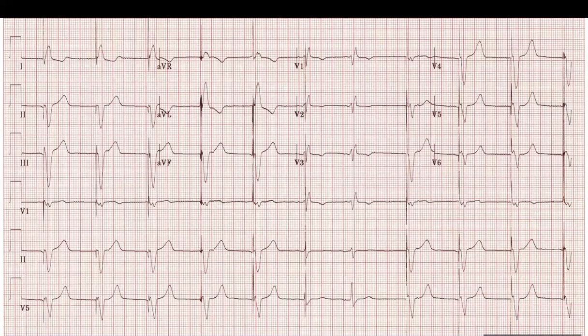Sensing most of the beats, except for this one, which is probably a normal safety pacing phenomenon. But this one, I was able to sense it. It inhibited pacing, and it waited for the appropriate amount of time between the QRSs to deliver the next impulse. So at least this is a single chamber pacemaker with normal pacing, capturing, and normal sensing.